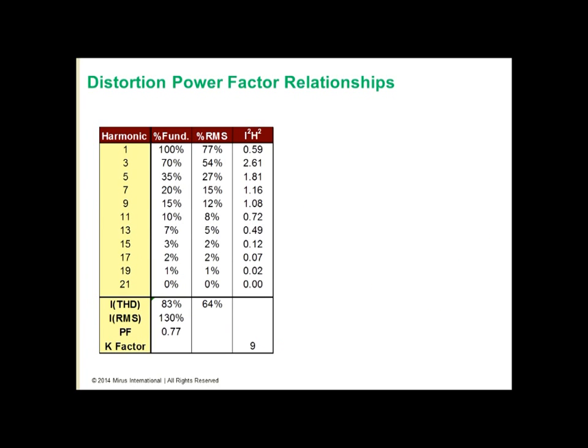In this slide, I use it to show the relationships between harmonics and power factor. So the first column is our harmonic number, starting with the fundamental being 1, and then we have the odd orders up to 21. The second column shows the percent of fundamental for each harmonic. So the fundamental current is 100%. The third harmonic here is 70% of the fundamental. The fifth harmonic is 35%. The next column I show is percent RMS.